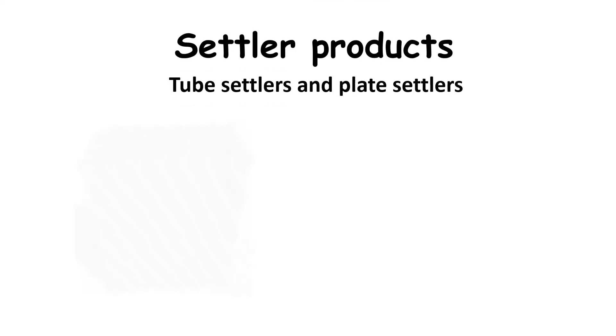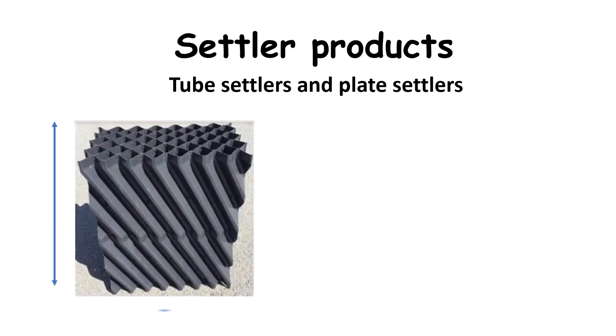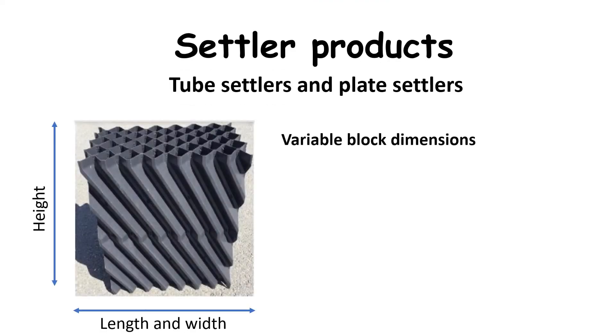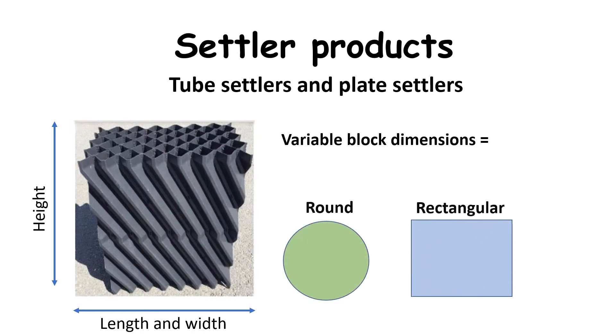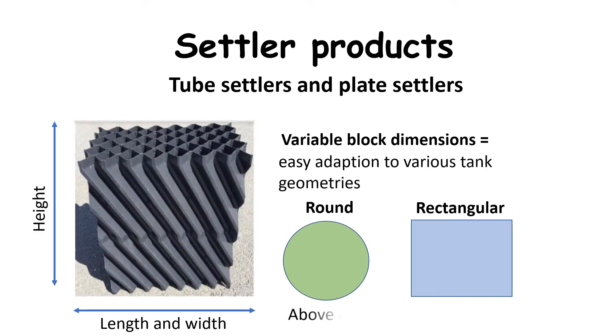Additionally, tube settler block dimensions can be configured to any basin size and geometry, which makes them also suitable for existing covered, underground, or round tanks. In contrast, plate settler modules are usually too large to fit into existing covered or underground tanks, and they cannot be used in most round tanks.